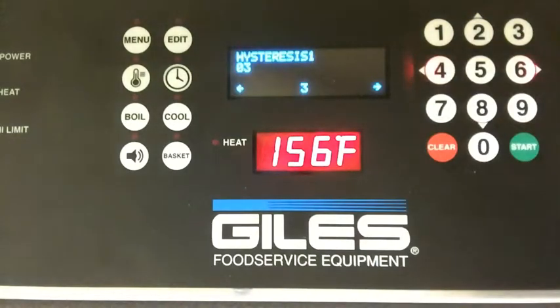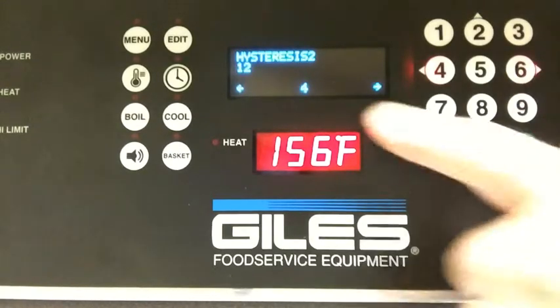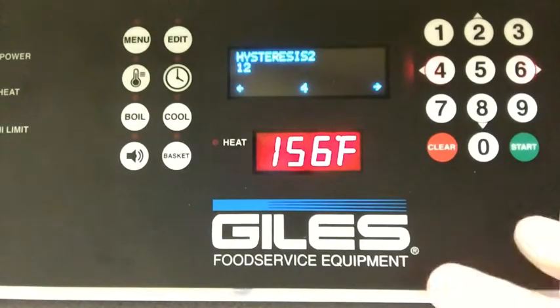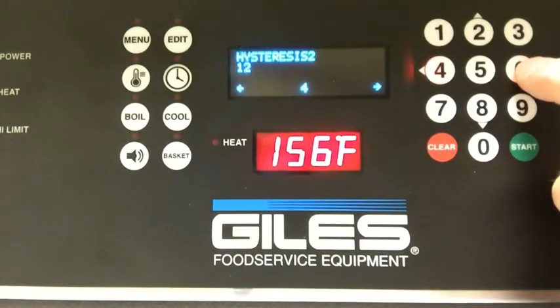The hysteresis is 3 degrees. At 3 degrees below set point, the heat will come on and it will run to set point. You could drop that down. On gas machines, we often run that at 6 degrees below because the recovery is so fast. But 3 degrees on an electric machine is pretty sensible and works extremely well. We also have a hysteresis 2. Now this is just for gas machines, has nothing to do with your EOFs.